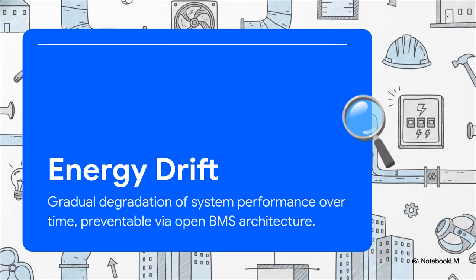By insisting on an open building management system architecture, using universal communication protocols like BACnet or Modbus, we can plug in artificial intelligence and digital twins to catch these anomalies early. Imagine a scenario where a system is heating and cooling the exact same room simultaneously because of a sensor conflict. An open BMS catches that flaw during the design and commissioning phase, preventing years of wasted energy.